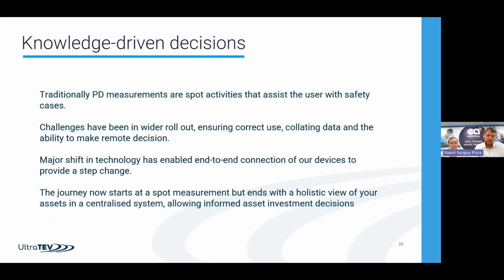Traditionally, PD measurements were purely there for a safety case, and that's still valid. If I was going to work alongside a piece of switchgear for the day, I'd do a quick PD survey - it takes a few minutes and gives confidence in the status. If I was going to switch, I'd certainly take measurements pre and post switching. That's purely from a safety point of view.